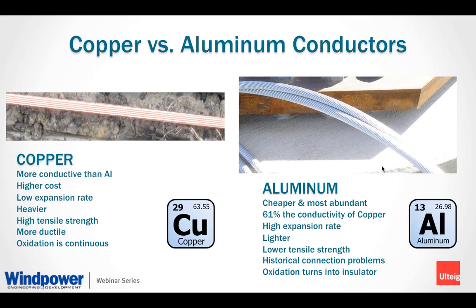You also need to consider expansion rates when you're connecting aluminum versus copper. These two metals don't like to be connected to each other. They have a type of chemical reaction that goes on, and they also have different expansion rates as they heat up. And this tends to be problematic. So there have been ways around this, where a transition metal has been used, such as tin, or the copper is made with aluminum, like a copper-clad aluminum.